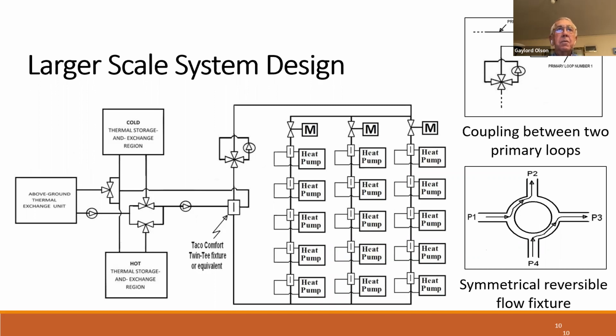from Taco Comfort, which you can find on their website. Type in Twin T. You'll see what it is. It's a special type of hydraulic separator, and it replaces two closely spaced T's, which is a more conventional way to couple two loops like this. But the nice thing about the Taco Comfort product, it's fully symmetrical, so you can have flow in either direction, either in this design, either horizontally or vertically. It doesn't really matter if the flow is one way or the other. It works all the same. And that's kind of important for the rest of this system here.